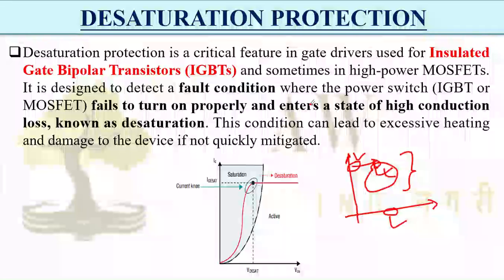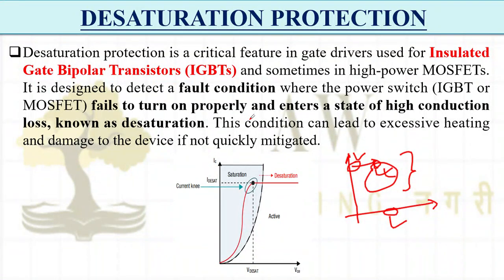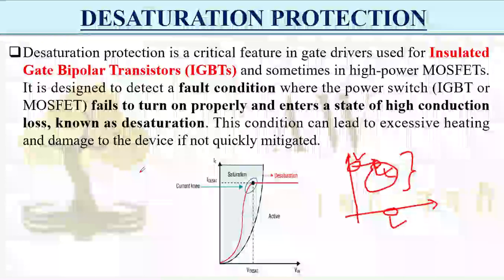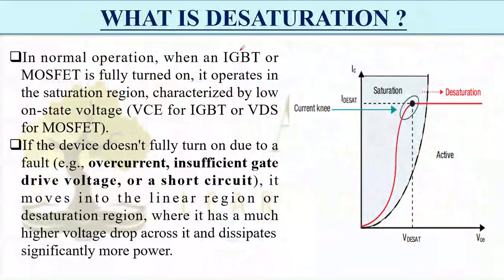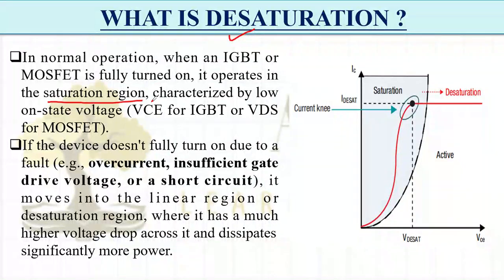This protection will not allow the device to go into the active region, where very high conduction losses occur. So desaturation protection prevents this. In normal operation, when an IGBT or MOSFET is fully turned on, it is operating in the saturation region, characterized by a low on-state voltage.